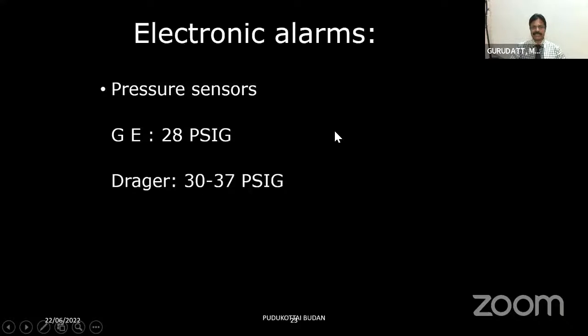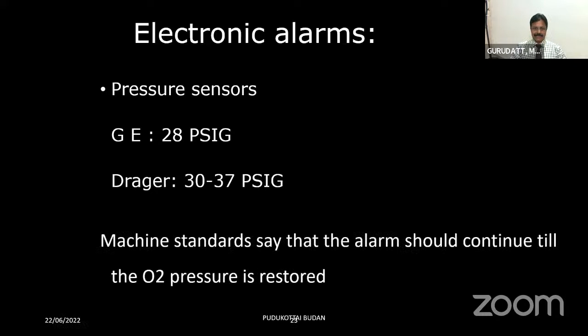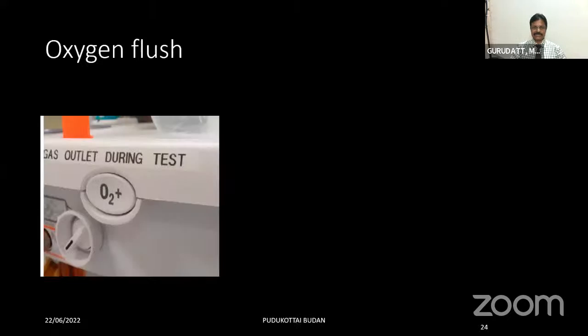An electrical connection is there, and we have electronic alarm systems because we have pressure sensors, which continuously sense the oxygen pressure. In GE machines, once the pressure comes down to 28 psig or less, the alarm will automatically start. And in Draeger, once the pressure drops to less than 30 or 37 psig, the alarm will get activated. And based on the standards, these alarms will continue till the oxygen pressure is restored. That's about the electronic alarms present in the modern workstations.